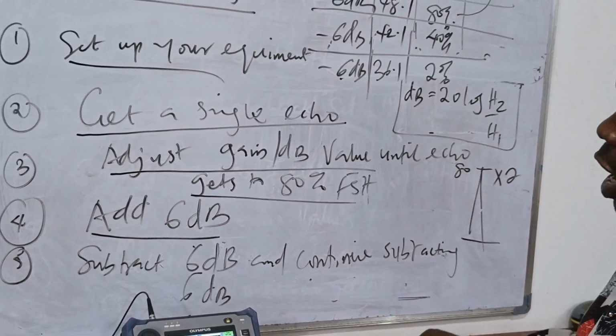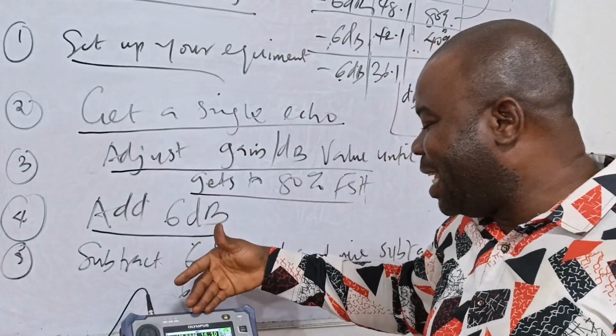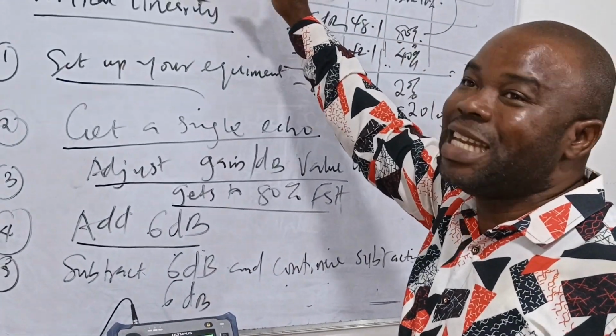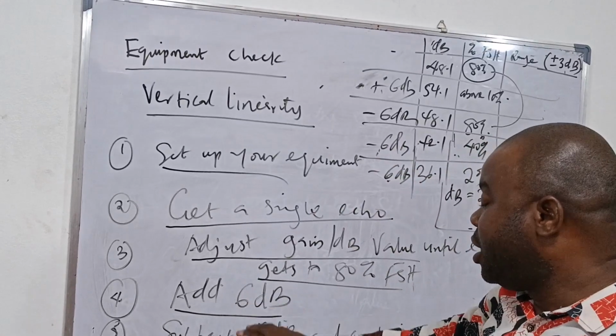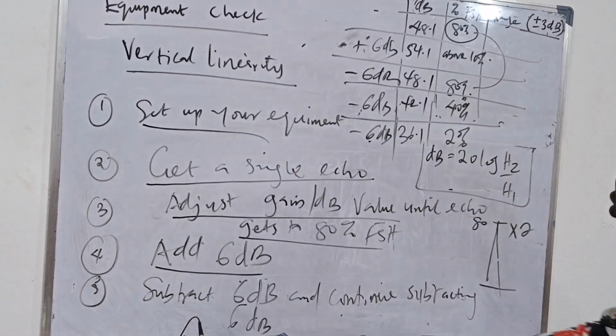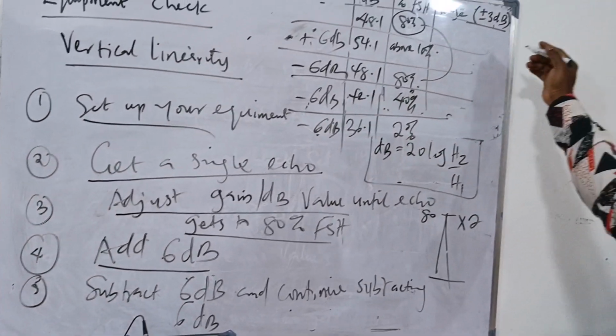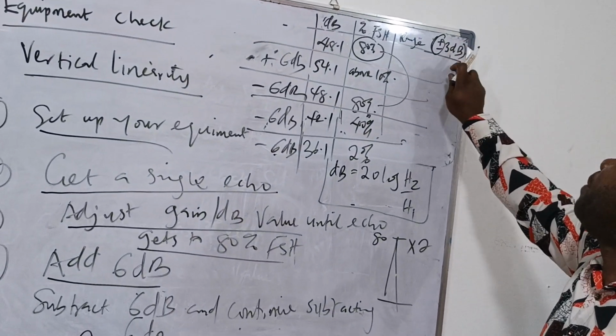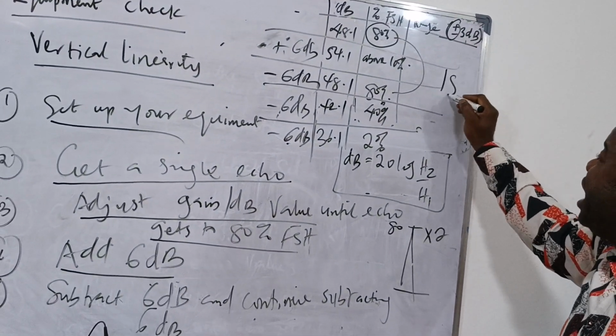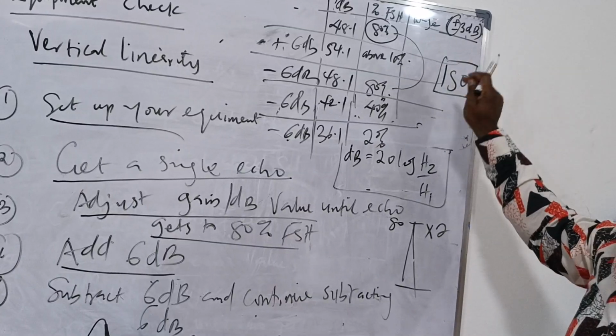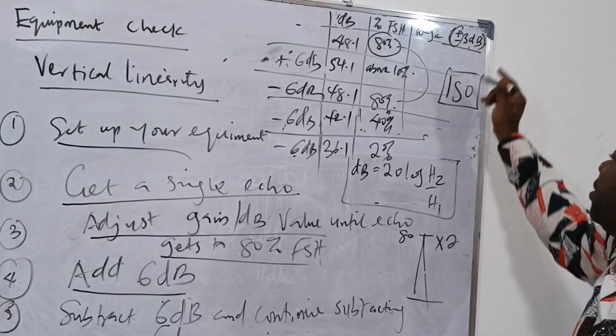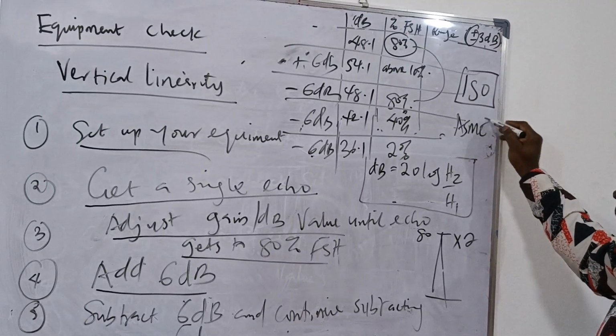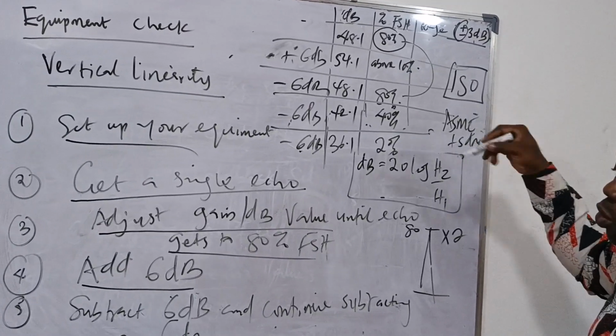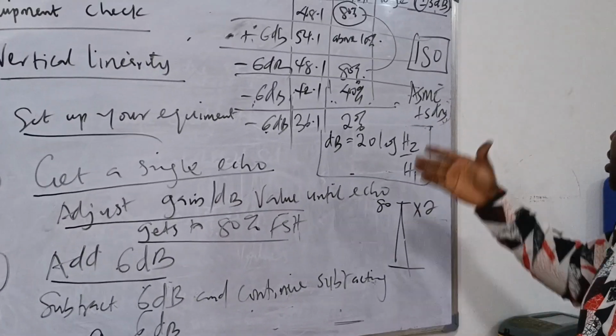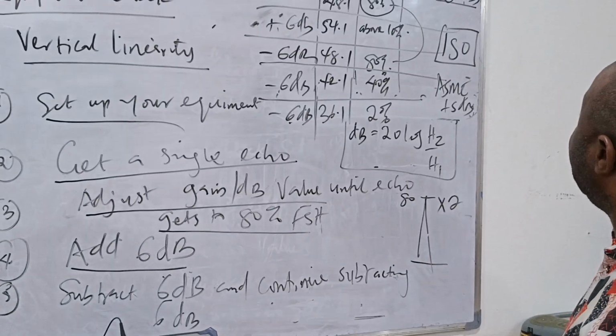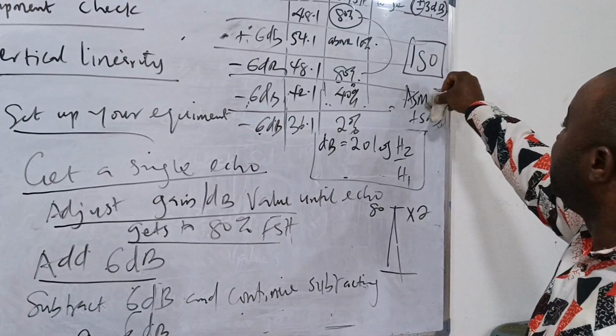Now, if you look at what I was explaining initially, at some point I was not getting exactly 80%. It is not an issue. That is why we have what we call the tolerance. For vertical linearity, the tolerance is usually plus or minus 3 dB. For ISO, take note, for ISO is plus or minus 3 dB. For ASME is plus or minus 5 dB. So depending on the standard that is guiding whatever job you are doing, note this dB value.